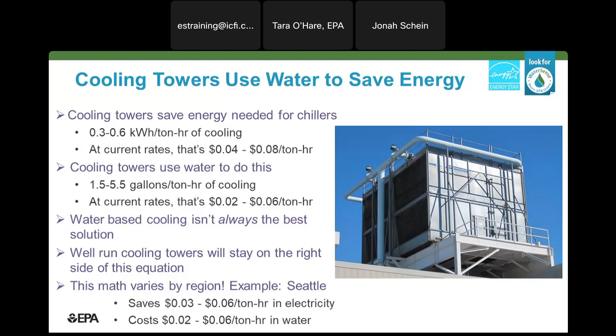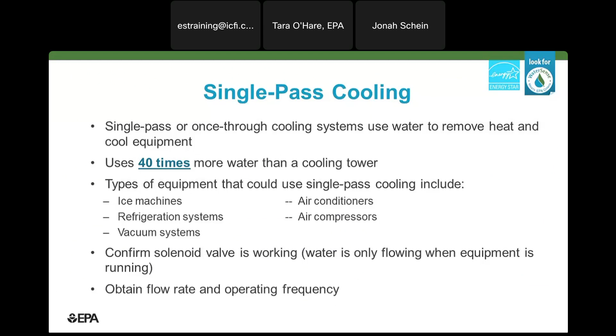The other thing, maybe I should have put this first, that we always emphasize: single pass cooling is not something we encourage. This is the reason we use cooling towers, so that we can use water-based cooling and still use that water more efficiently. If we're using single pass, then you're really just using that water once and then running it down the drain. So a cooling tower can be about 40 times more efficient than single pass cooling because of its ability to circulate that water around and reuse it multiple times.